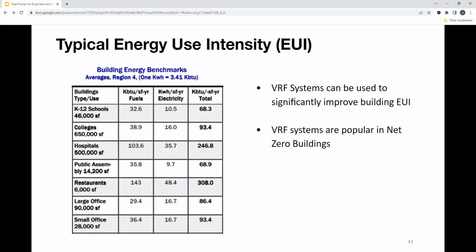I just want to mention also that VRF systems are used to significantly improve the EUI, which is your energy use intensity, right? So a lot of the time, VRF systems are popular in net zero buildings or looking to go net zero. And that's because you need an EUI that's roughly around 15 to 20 kBTU per square foot per year, which also considers the use of solar panels as well.